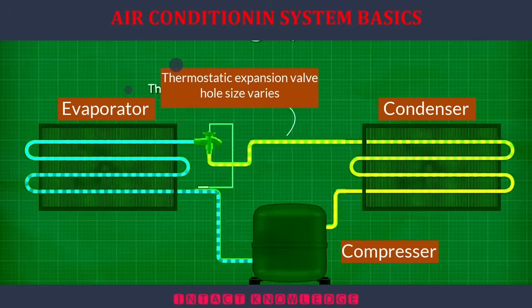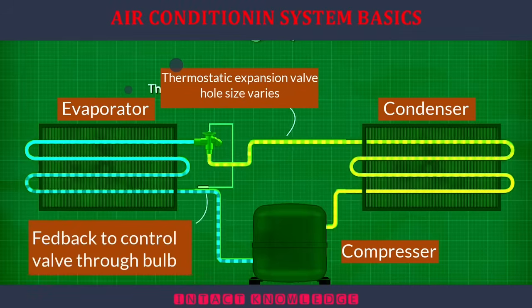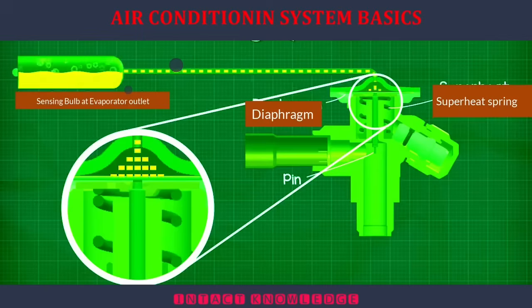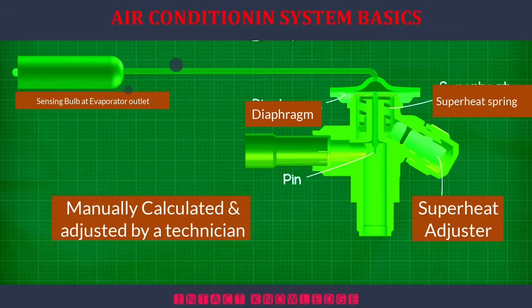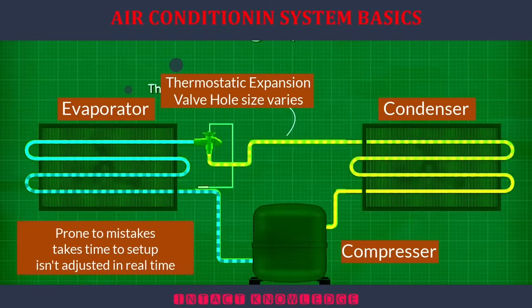This is still widely used today, and it senses the superheat at the outlet through a bulb which is filled with another refrigerant. This other refrigerant will expand to open the valve when the superheat is too high, and it condenses to close the valve when the superheat is too low. This type of valve needs to be manually calculated and adjusted by a technician. It does work very well, but it's prone to mistakes.